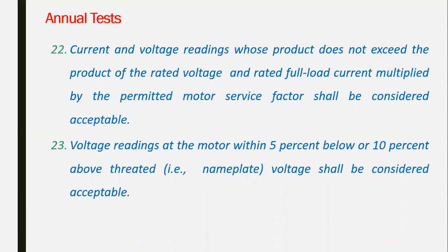During operation, you have to check the current and the voltage rating, and they have to match the nameplate and the rated current and operational voltage as per the data sheets of the pump itself. The nameplate of the pump has to indicate the current and operating voltage. Get the readings of the current and the volts and compare them with the nameplate and data sheets of the pump. The voltage rating at the motor should be within 5% below or 10% above, so minus 5 and plus 10% of the voltage. It should not affect the operation of the pump.